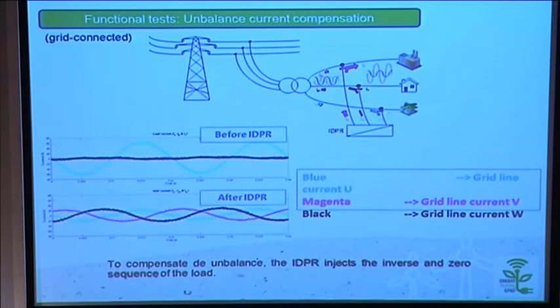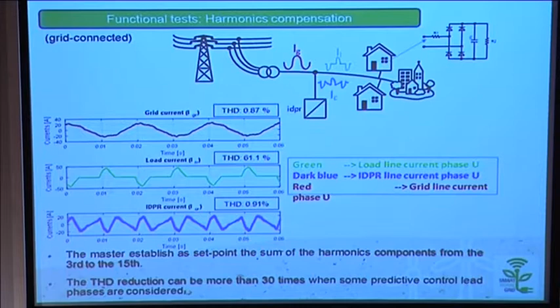Another example, also in grid connected mode: we can have an aggregated load that at the end supposes a really nonlinear load. This is an extreme situation, but imagine that we have a load with this profile that represents about 61% of THD in terms of current. The IDPR is able to supply all the harmonic components except the 50 Hertz component, which is supplied directly by the grid. So the grid sees less than 1% of distortion, and all the distorted components are supplied by the IDPR. This is all for the grid-connected mode, but what about the grid-disconnected mode?